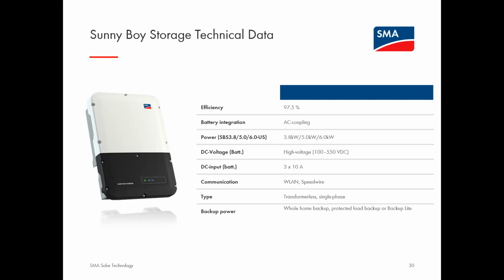This also really helps make the system quite future-proof because, of course, battery technologies are continuing to evolve and voltages are getting higher and higher. So we have quite a wide operating range of batteries that we can accept on the DC input side. And because we have 3 dedicated inputs on the SunnyBoy Storage, these were the inputs that were formerly maximum power point trackers on the PV inverter, you can actually mix and match batteries of different voltages, make and model, and so on and so forth. That's completely unique to SMA's energy storage offering. No other technology out there in the market that we're aware of allows you to mix and match batteries. Again, that's really helpful for ensuring you have a future-proof energy storage system if your customers want to add capacity over time.